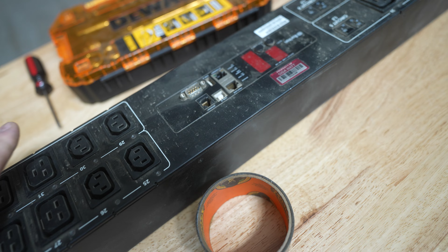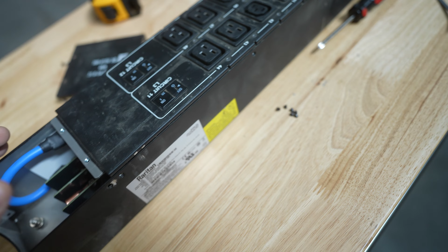We can't just use every single one of these plugs, because that'll give us way more than 35. The maximum load here is 35,000. The PDU will trip, and your gauge will not be able to handle it. We're plugging in 6 gauge here. So 6 gauge is coming in on all 3 phases here, and the neutral and the ground.